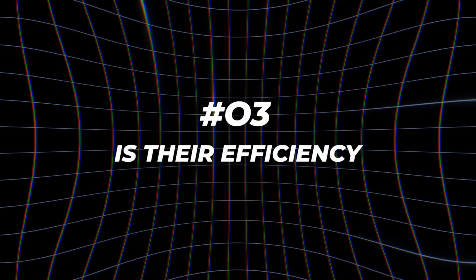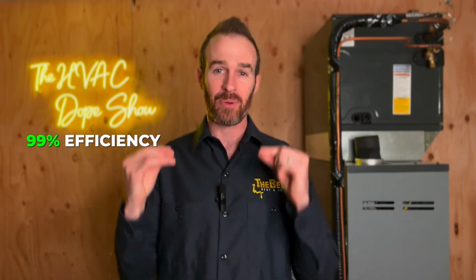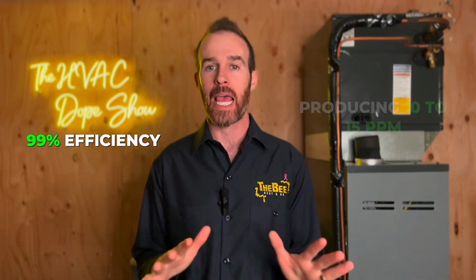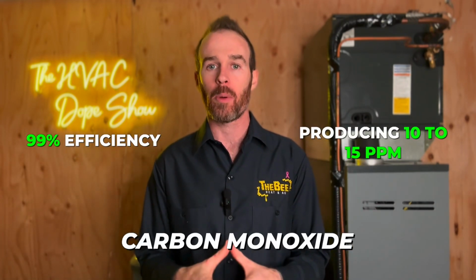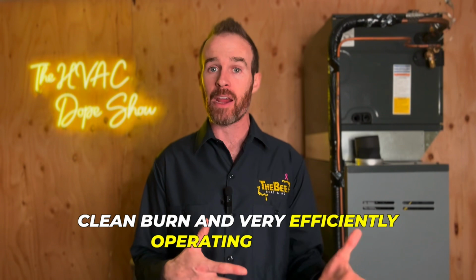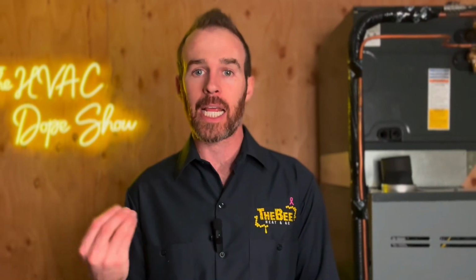Part number three is their efficiency. When we did a combustion analysis on these bad boys, they were running at 99% efficiency and producing 10 to 15 ppm of carbon monoxide. For anyone who is not a contractor watching this, in layman's terms, this is an extremely clean burn and a very efficiently operating system. This is proof that their technology is superior, because in order for me to get a clean burn, I did not have to manually adjust my mixture or set a mixture screw.